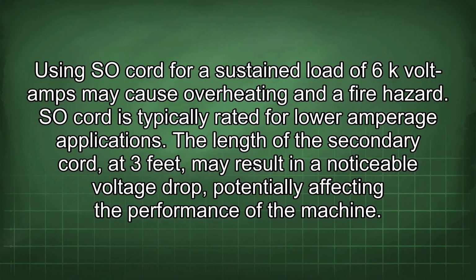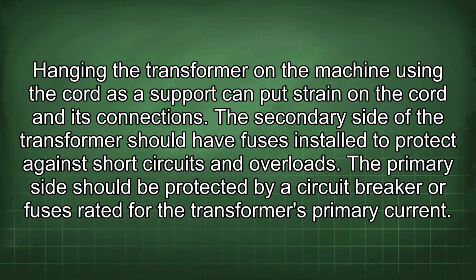Using SO cord for a sustained load of 6 kVA may cause overheating and a fire hazard. SO cord is typically rated for lower amperage applications. The length of the secondary cord, at 3 feet, may result in a noticeable voltage drop, potentially affecting the performance of the machine. Hanging the transformer on the machine using the cord as a support can put strain on the cord and its connections. The secondary side of the transformer should have fuses installed to protect against short circuits and overloads. The primary side should be protected by a circuit breaker or fuses rated for the transformer's primary current.